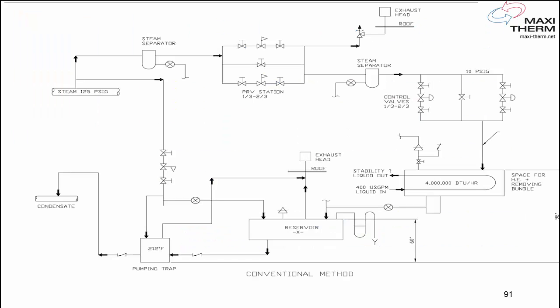Before we talk about Maxitherm technology, I just want to go through some of what we've been doing for the last 100 years. This is a typical steam drawing for a steam process heat exchanger right here, heating a liquid — it can be water or glycol. A typical design has high-pressure steam coming in on top. We reduce the pressure to 15 psi with a 1/3–2/3 pressure-reducing valve station. Then we need a safety valve vented to the roof and a 1/3–2/3 control valve at the inlet of the heat exchanger.